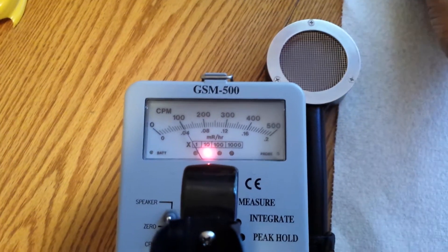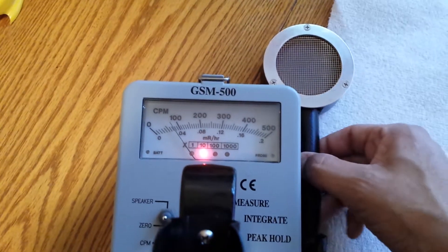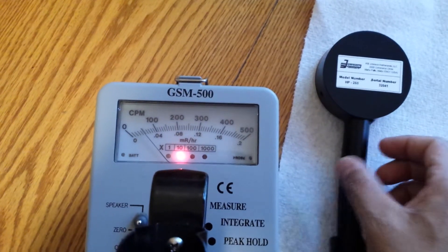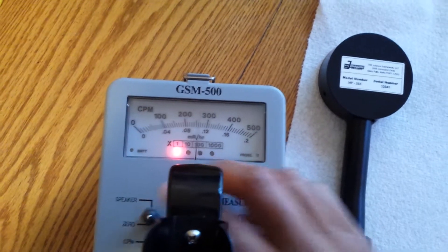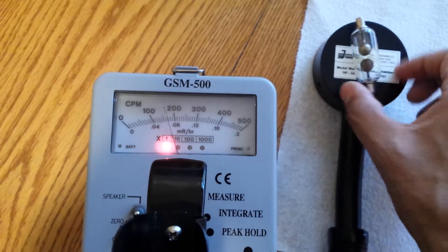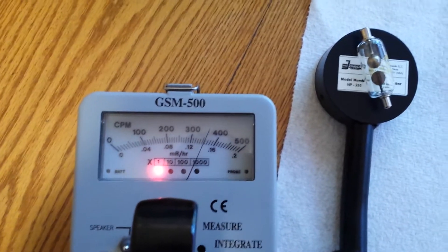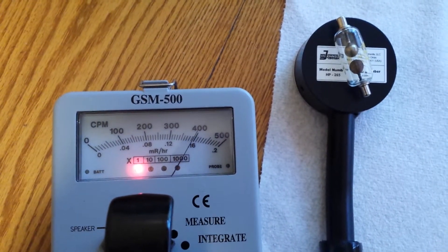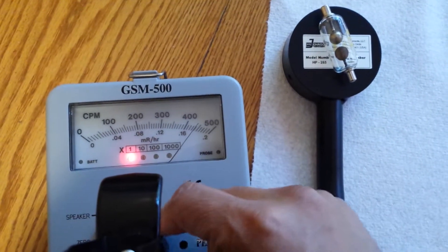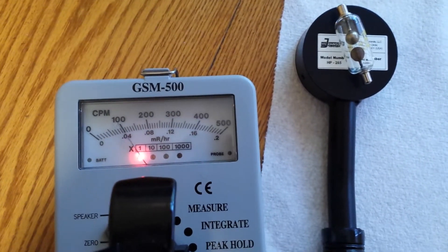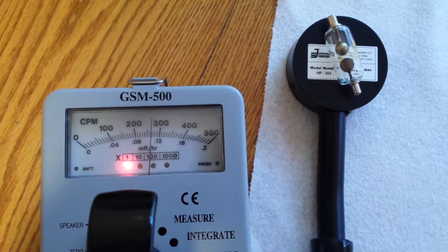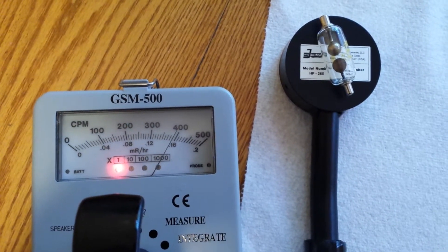Now let's see how much of that is gamma. I'll flip this over. I'll do a reset and let's see how much gamma we have. Let me go to peak hold. Peak hold holds the needle without moving back and forth.